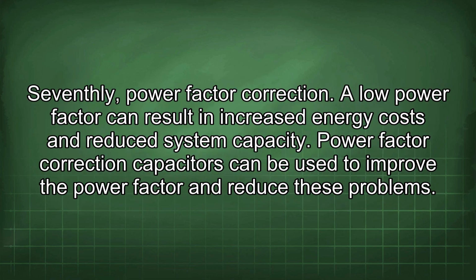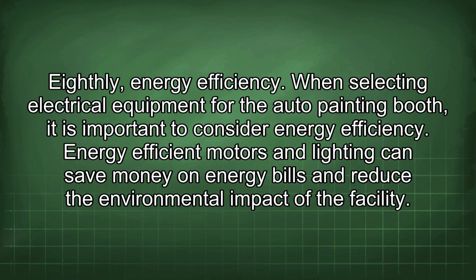devices. Seventhly, power factor correction. A low power factor can result in increased energy costs and reduced system capacity. Power factor correction capacitors can be used to improve the power factor and reduce these problems. Eighthly, energy efficiency. When selecting electrical equipment for the auto painting booth, it is important to consider energy efficiency. Energy efficient motors and lighting can save money on energy bills and reduce the environmental impact of the facility.